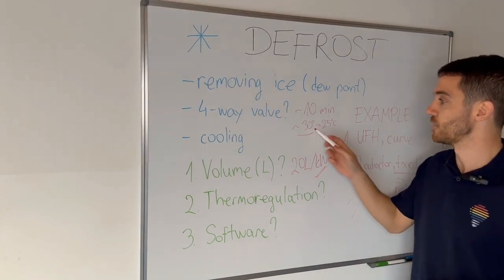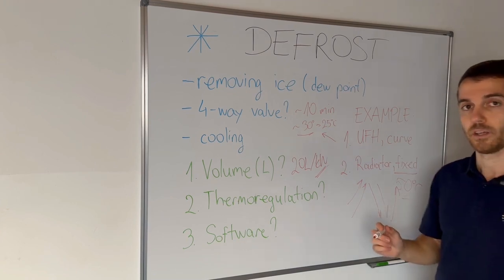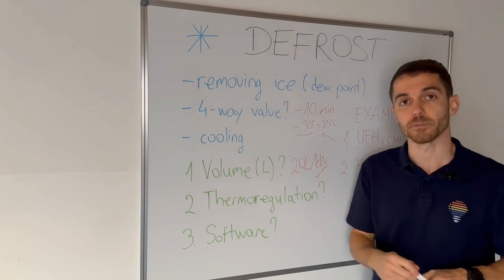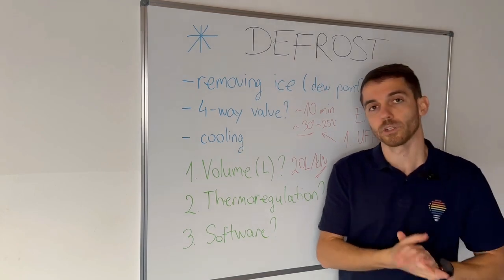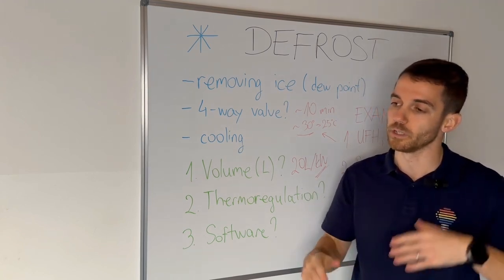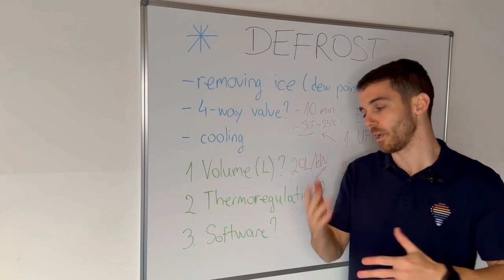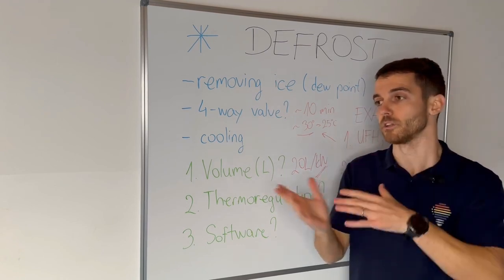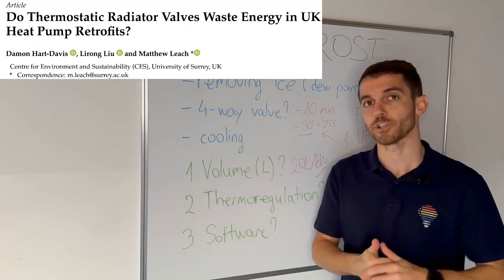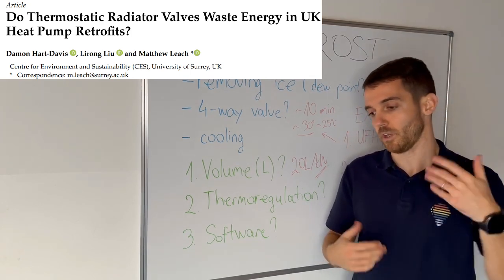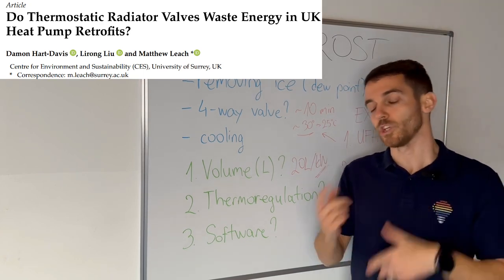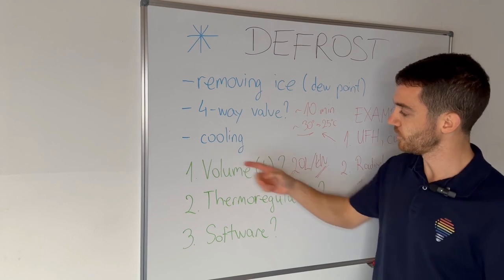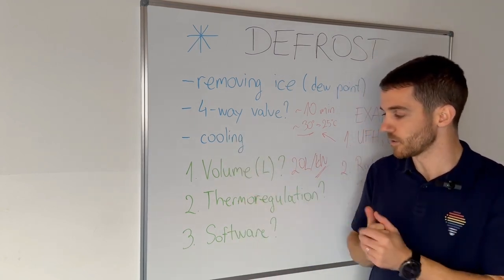You can imagine it like driving a car at 60 km/h versus 150 km/h — you spend more fuel at 150 and you cannot brake as quickly as at 60. So volume is really important, thermoregulation is important, and basically how you drive your system matters. If you drive your system slowly for a long period of time, you will have better efficiency. For some people this is counterintuitive — they think turning off the system will reduce energy consumption. But you will actually spend more on electricity from the compressor, and also on defrost cycles, switching points, cooling the water, and then heating up again. If you follow points one and two, software — point three — will take care of your defrost cycle.